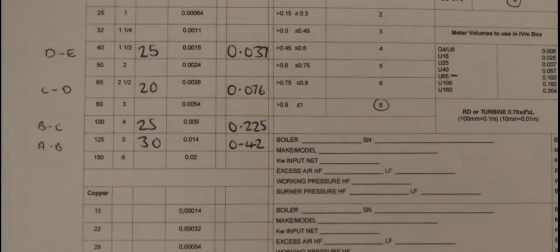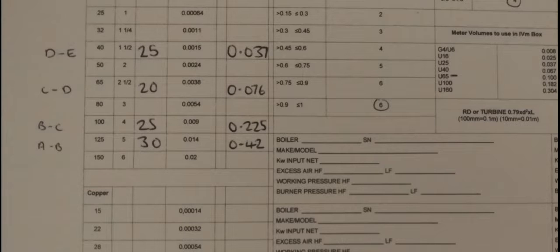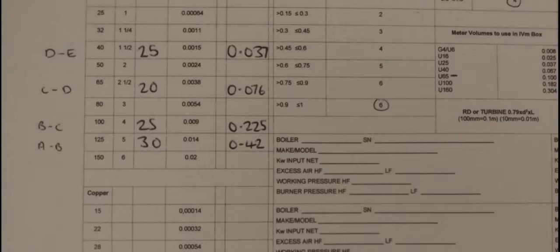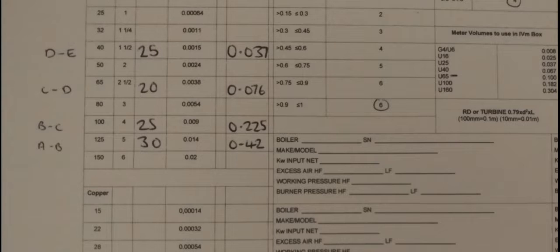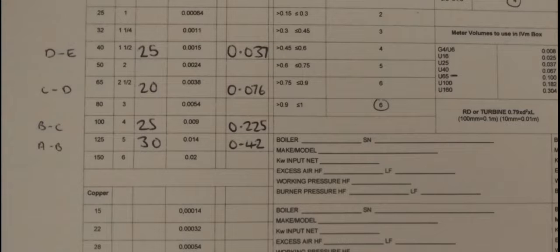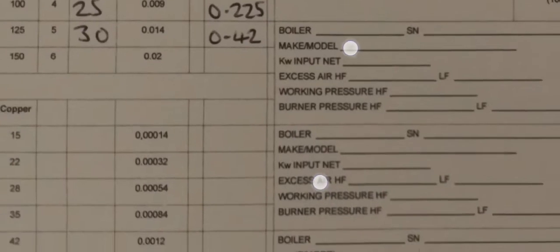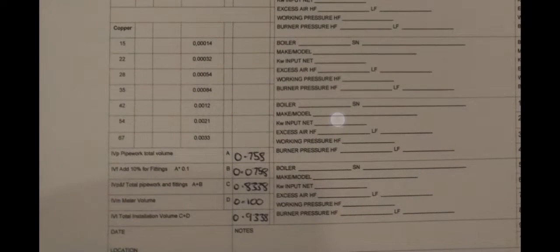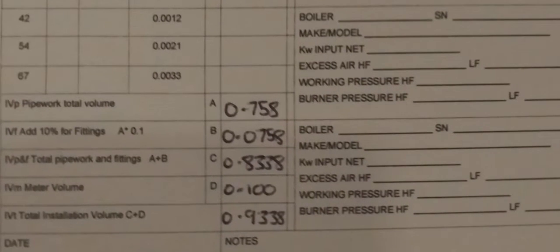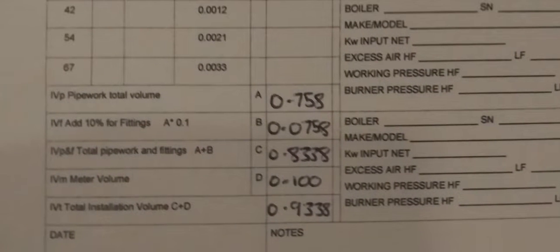D to E is 25 meters of 40 millimeter pipework. I have times my 25 by my 0.0015 and got my answer here. Then when I'm finished with each of the sections, I add them up and I will come up with my answer down here - my IVP. Then remember there are different ways you can get your 10 percent.